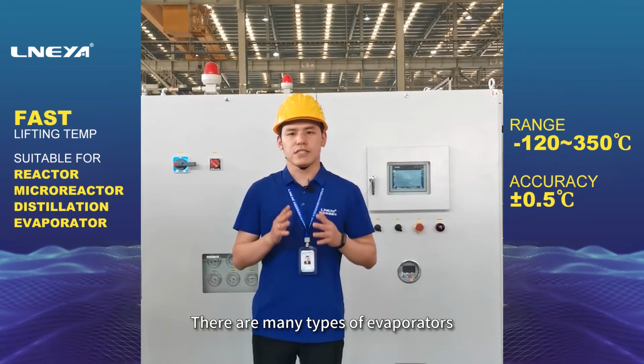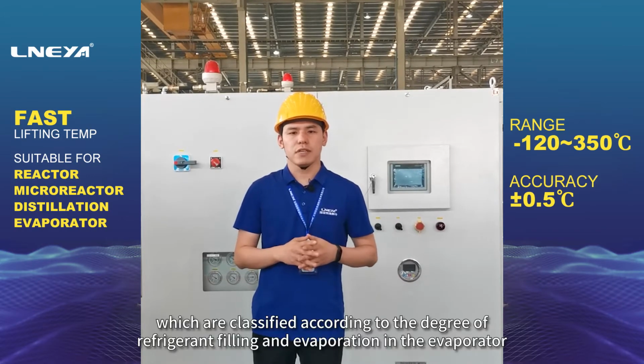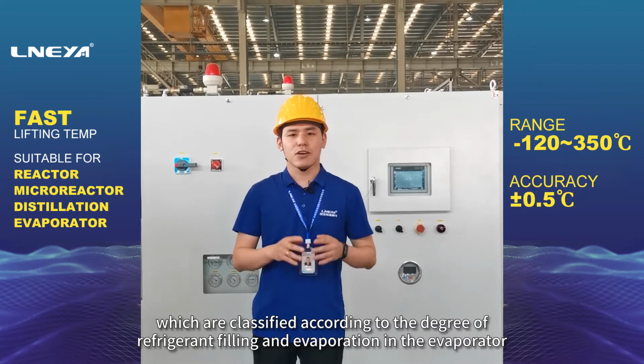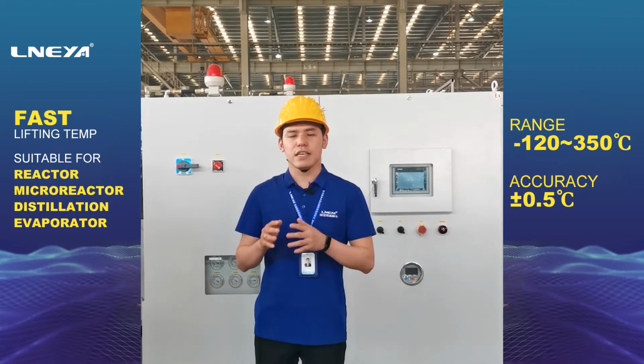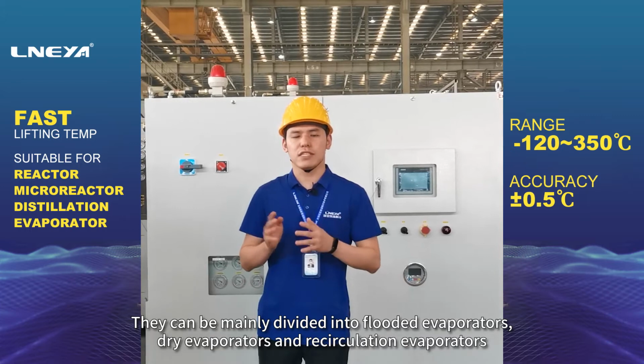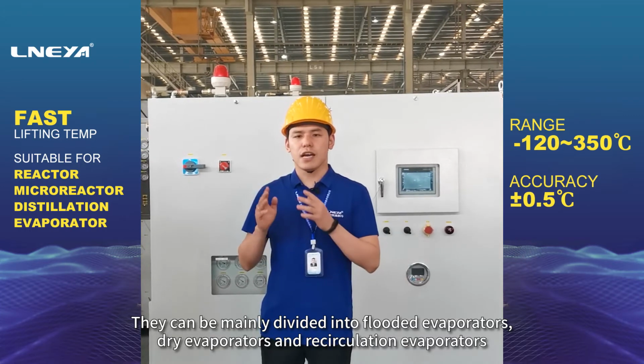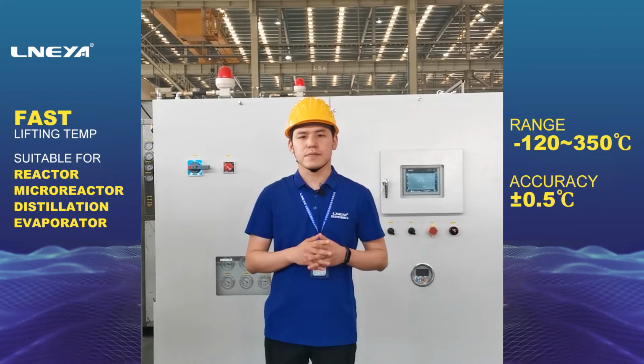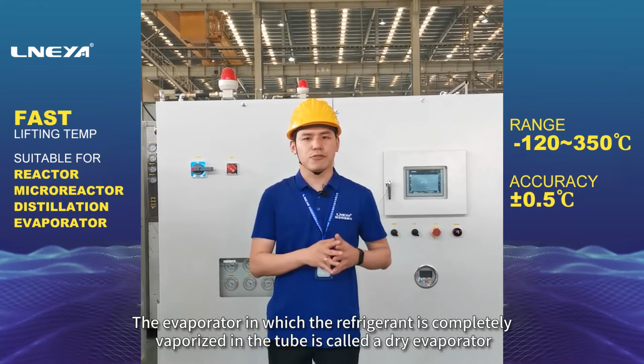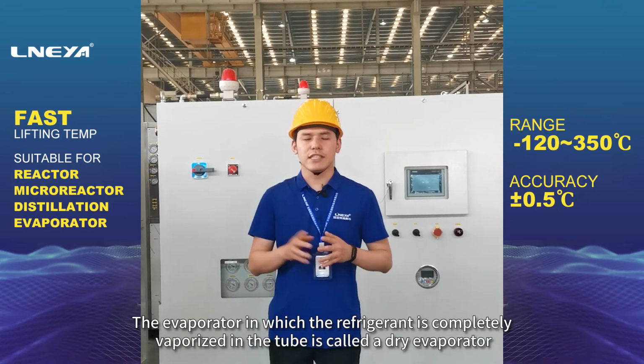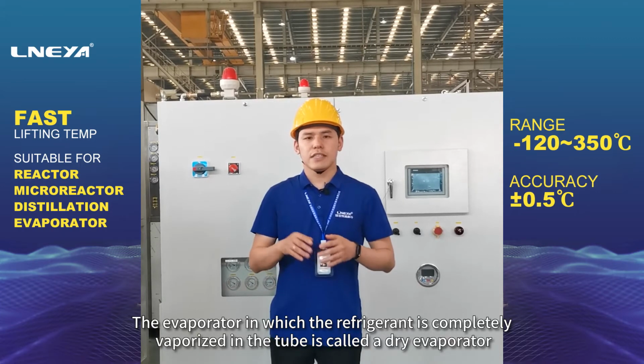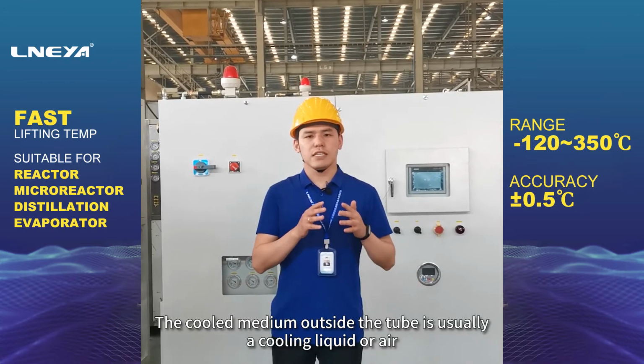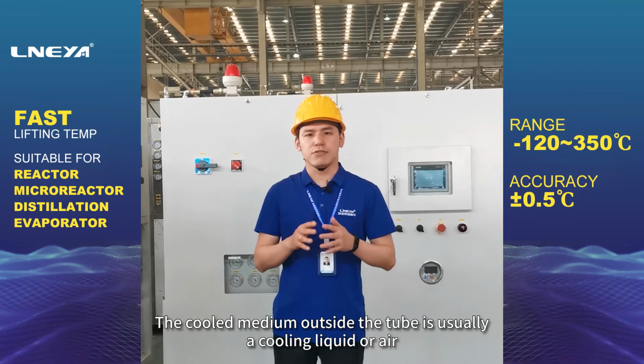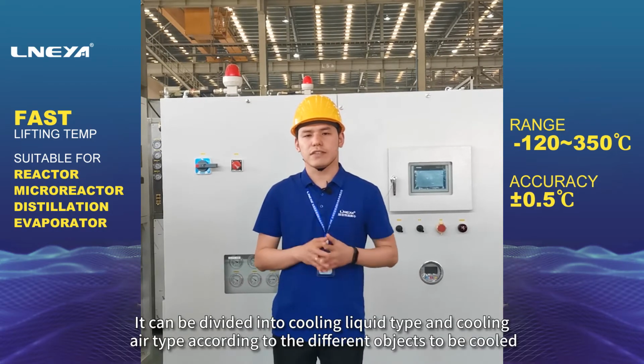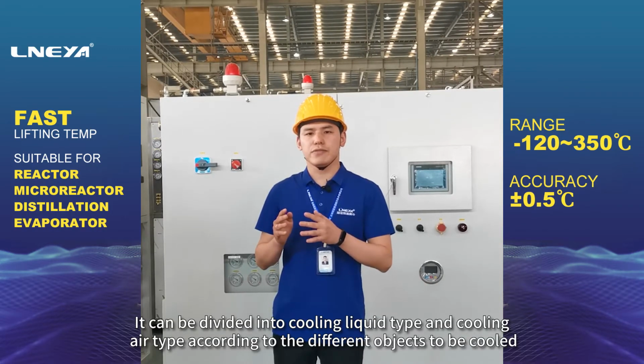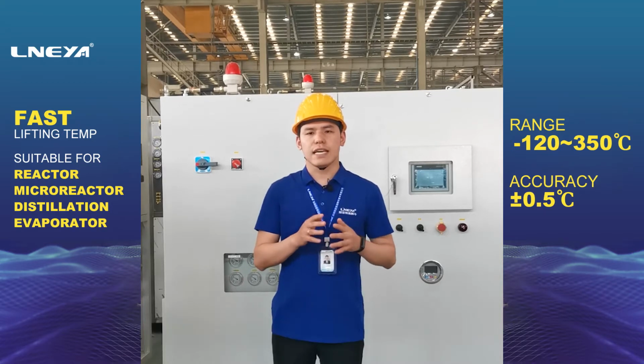There are many types of evaporators, which are classified according to the degree of refrigerant filling and evaporation in the evaporator. They can be mainly divided into flooded evaporators, dry evaporators and recirculation evaporators. Dry evaporator. The evaporator in which the refrigerant is completely vaporized in the tube is called a dry evaporator. The cooled medium outside the tube is usually a cooling liquid or air. It can be divided into cooling liquid type and cooling air type according to the different objects to be cooled.